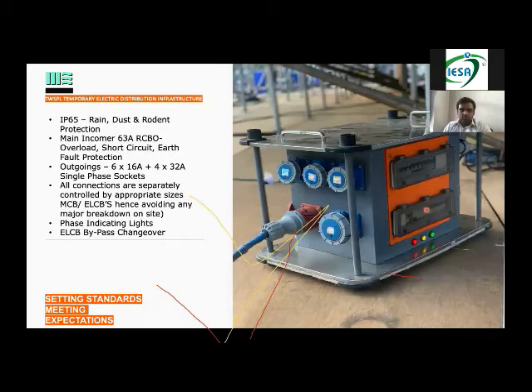So normally what happens during the setup, all the safeties are on. Everything is on during the setup, so we try to eliminate problems. If somebody is bringing a faulty microwave, maybe a LED wall is faulty, maybe a light is faulty, our system keeps on tripping, which is good because it is for safety. During the show day, we switch off all the safeties because till the setup, we have already eliminated 99.9% of problems. So on the show day, maybe for those 12 hours or maybe for those 4 or 5 hours, we do a changeover of all our safeties. Though it is not recommended, till the time everybody doesn't get educated that this tripping is for safety, and it is not that the system trips a lot, your electricity is at fault.